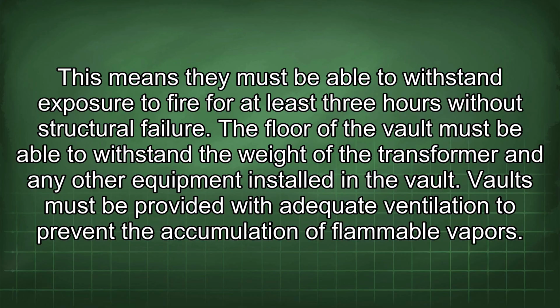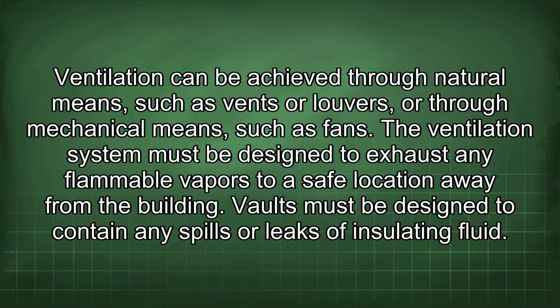structural failure. The floor of the vault must be able to withstand the weight of the transformer and any other equipment installed in the vault. Vaults must be provided with adequate ventilation to prevent the accumulation of flammable vapors. Ventilation can be achieved through natural means, such as vents or louvres, or through mechanical means, such as fans. The ventilation system must be designed to exhaust any flammable vapors to a safe location away from the building.